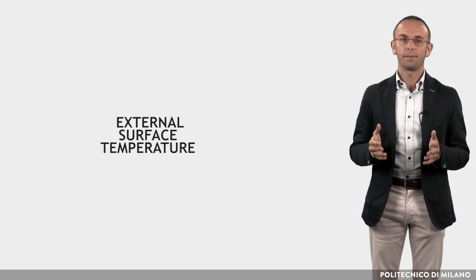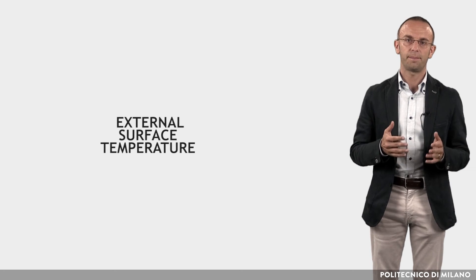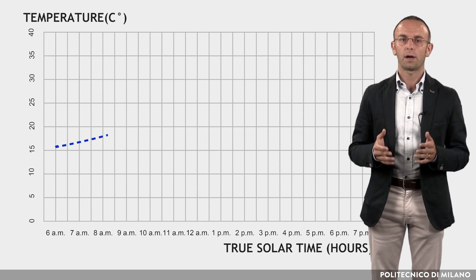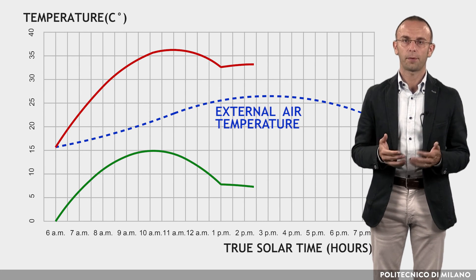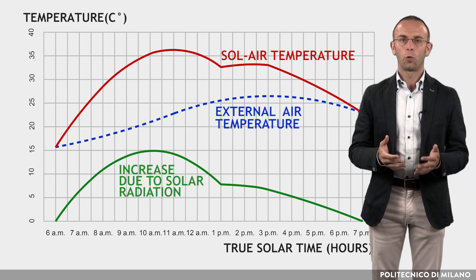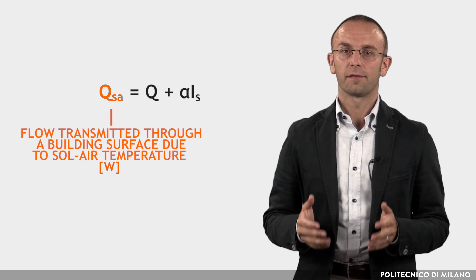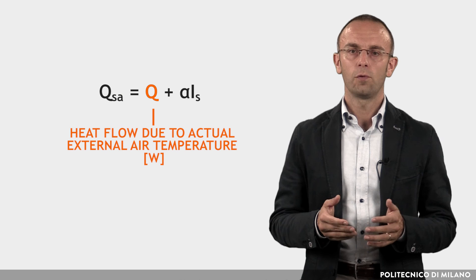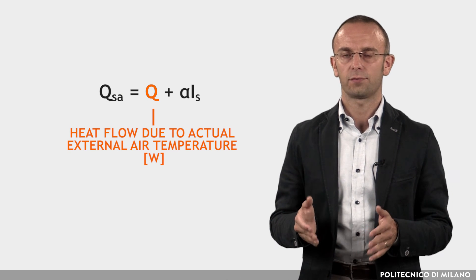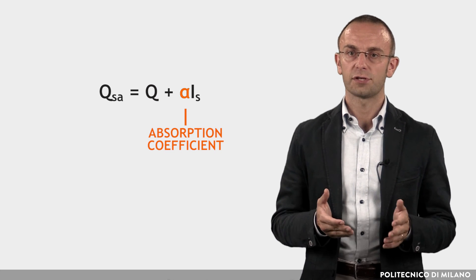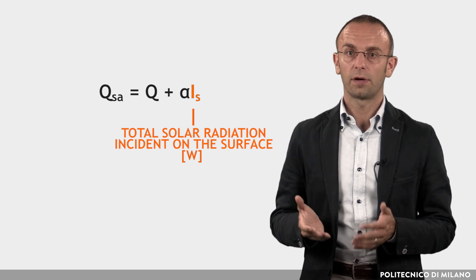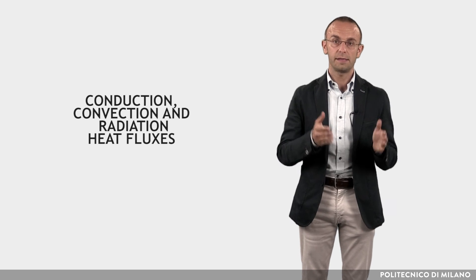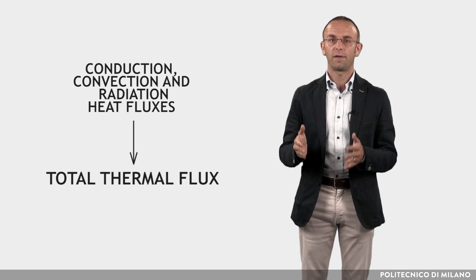When the surfaces of a building are hit by solar radiation, the external surface temperature increases depending upon the incident solar radiation and the absorption of the surface. This phenomenon can be taken into account by virtually increasing the external air temperature to an appropriate value to obtain the same effect. This increased value is called sol-air temperature. The heat flow transmitted through a building surface due to sol-air temperature, QSA, can be calculated with this formula, where Q is the heat flow due to actual external air temperature in Watts, α is the absorption coefficient of the surface (dimensionless), and IS is the total solar radiation incident on the surface in Watts. In conclusion, by calculating the conduction, convection, and radiation heat fluxes, it is possible to evaluate the total thermal flux through a building surface.